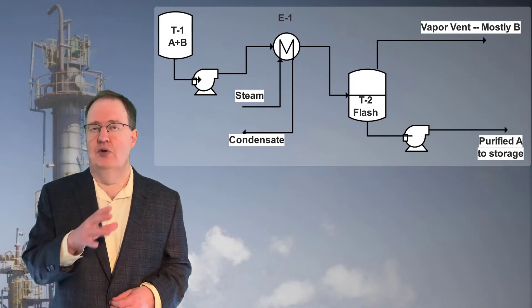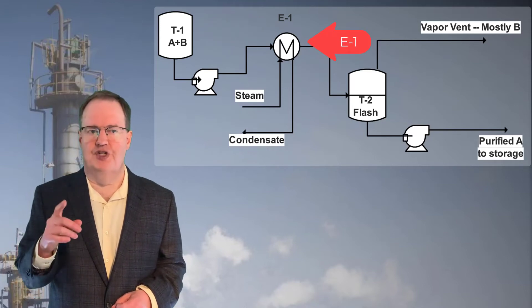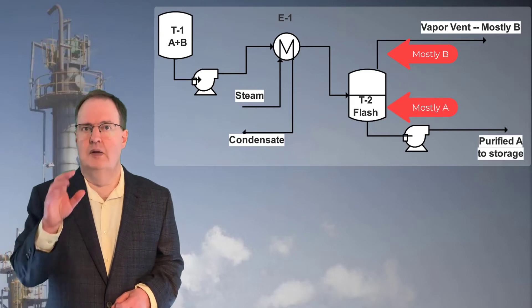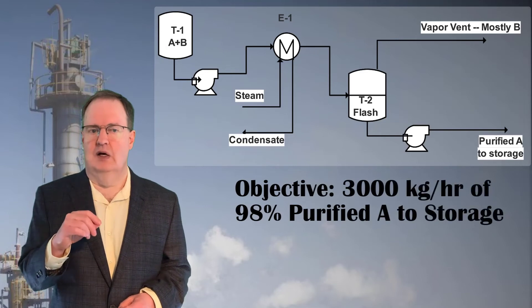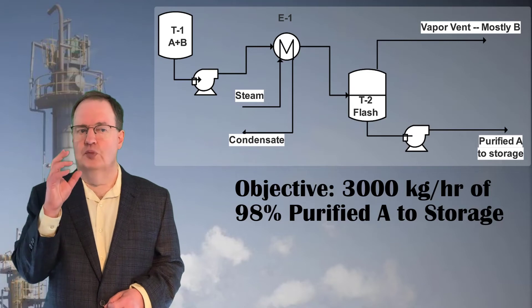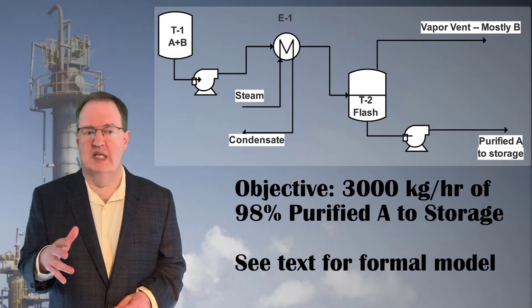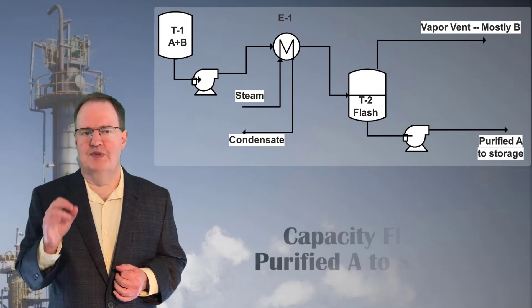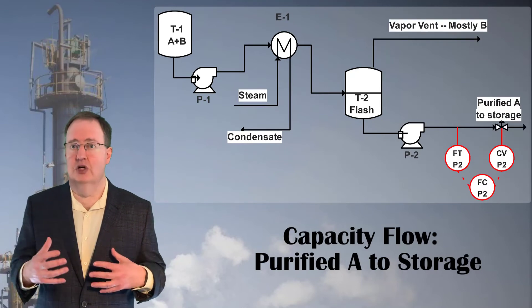Let's look at a second, slightly more complicated example: a flash tank. Here, heat is applied to a binary mixture of A and B from T1 using the steam heat exchanger E1. When the mixture of A and B reaches T2, some of it vaporizes, forming a mostly-B vapor stream and a purified-A liquid stream. B clearly has a higher vapor pressure than A. The objective for this flash tank unit is to deliver 3,000 kilograms per hour of 98% purified A to storage. The formal mass and heat balance consists of 18 variables and 9 initial equations, so let's tackle it with the heuristic method. The capacity flow is the specified fixed flow of 3,000 kilograms per hour for the purified A liquid leaving the flash tank bottom — we'll need to measure and control that flow first.